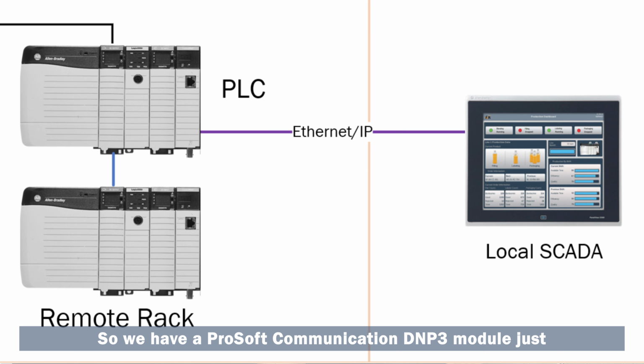We have a ProSoft Communication DNP3 module just over here. It acts as a communication gateway between different protocol types. We have DNP3 signals coming through from our GeoSCADA server, and this ProSoft module converts that into different formats and sends it over to other devices that use different protocols. That's why the ProSoft module is really useful in this case.